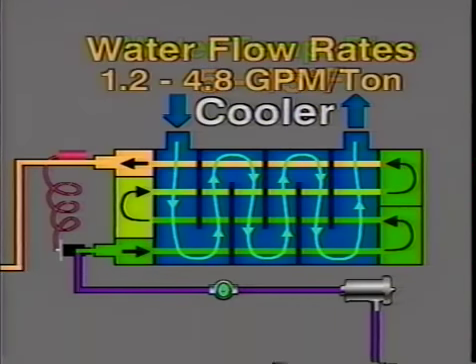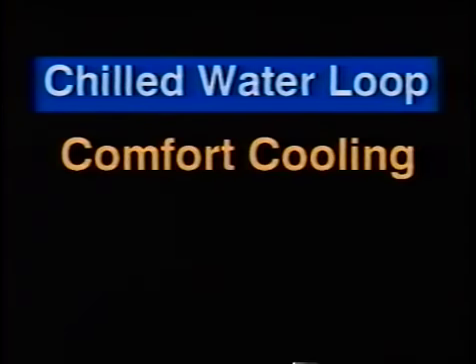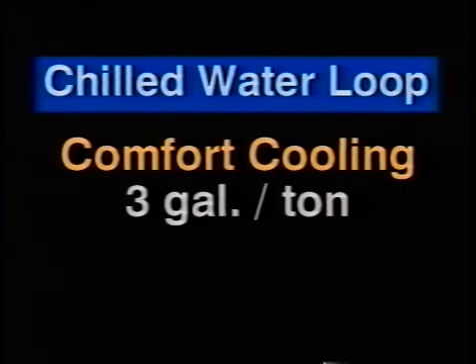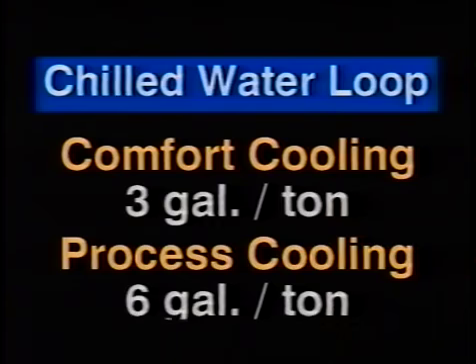Water flow rates for the cooler will generally range from 1.2 to 4.8 gallons per minute per ton. This flow rate will have been established on the basis of capacity and pressure drop when the equipment was originally selected. In order to have satisfactory temperature control, it's important that the chilled water loop is correctly sized. A good rule of thumb is that loop volume size should be not less than 3 gallons per ton of capacity for comfort cooling and 6 gallons per ton for process cooling.